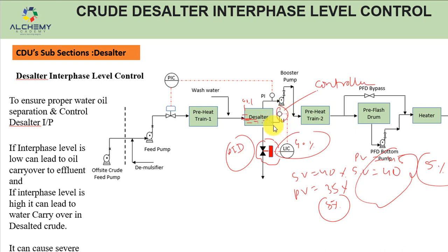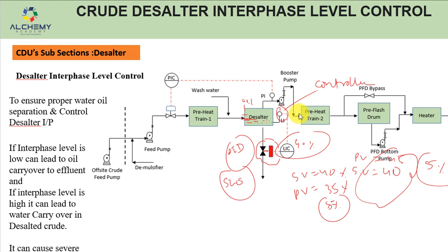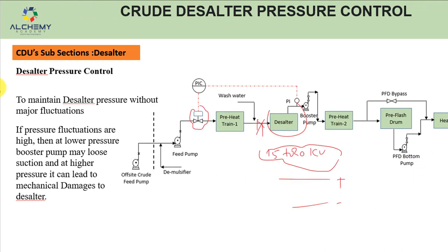If we don't control the desalter level, the consequences are serious. If the interface level is too low, oil can carry over to the effluent and go to the sour water stripping unit, causing a severe upset there since only sour water should be sent. If the water level is too high, water can carry over to the downstream atmospheric column, causing a water shot and a sudden pressure surge that can create a major upset in the atmospheric column. That is why desalter level control is critical.